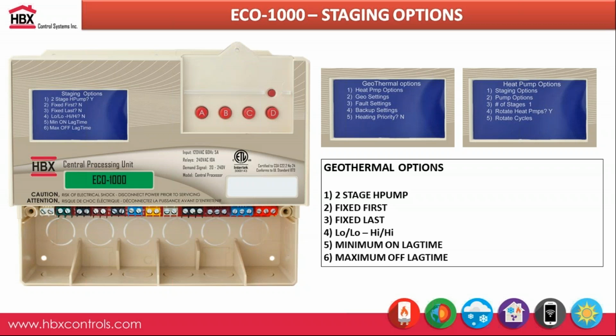Other options within your geothermal options in terms of your heat pump, you have the options to use 2-stage heat pumps. So if you were to select one 2-stage heat pump, that means your first 2 contacts on the XP or your ECO-1000 is going to be for that 1 heat pump, and then stage 1 and stage 2 is going to be for that second stage heat pump.